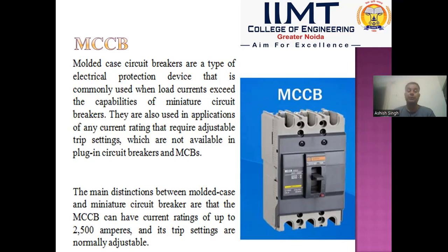The main distinction between molded case circuit breaker and MCB is the current rating. MCCB is used for current rating more than 63 ampere up to 2500 ampere, while MCB or miniature circuit breaker is used from 0.5 ampere up to 63 ampere. And the second one is its trip setting. In case of MCCB, adjustable trip setting is there, but in MCB no trip setting is given.